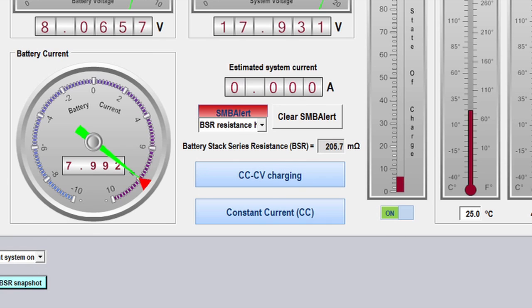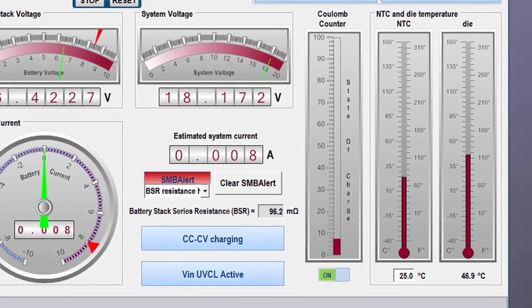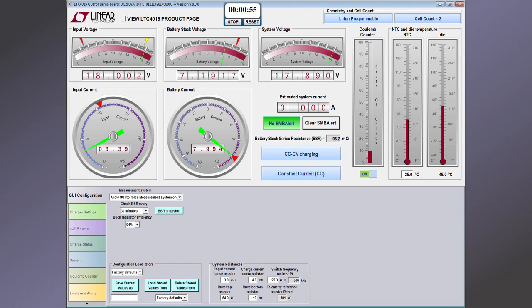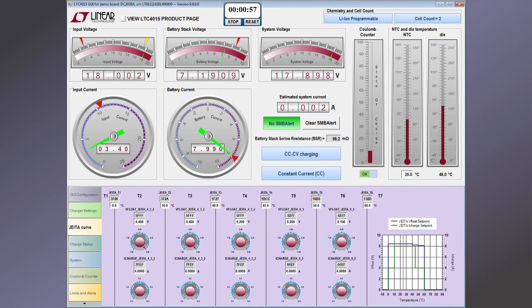I can reduce the series resistance, take a BSR measurement, and clear the alert. Now let's check back on the Coulomb counter. The stopwatch indicates that about 45 seconds have passed and you can see that the Coulomb count has increased from its initial value of 0% to about 7 or 8%. Perfect.